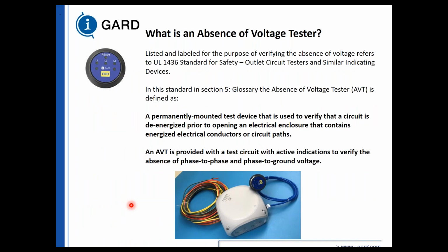The i-Gard absence of voltage tester is listed and labeled for the purpose of verifying the absence of voltage to UL 1436. The standard in section 5 says a permanently mounted absence of voltage tester is to verify the circuit is de-energized prior to opening the electrical enclosure that contains energized electrical conductors or circuit paths. An absence of voltage tester is provided with a test circuit with active indication to verify the absence of phase-to-phase and phase-to-ground voltage.